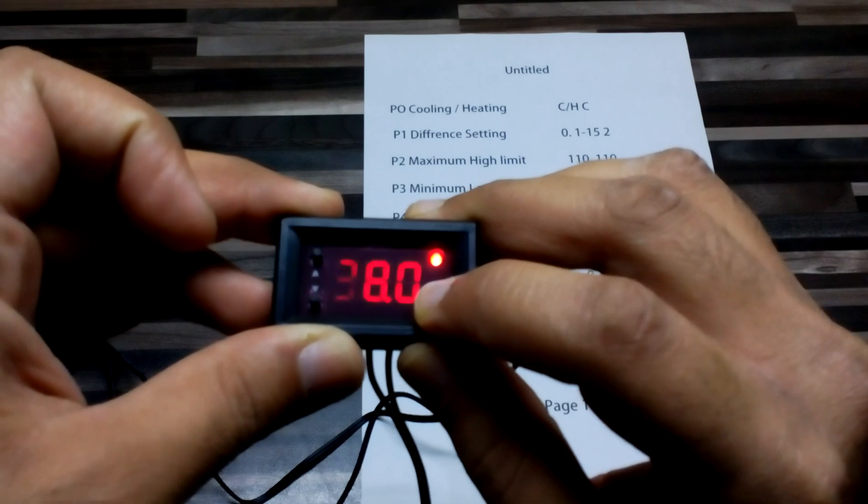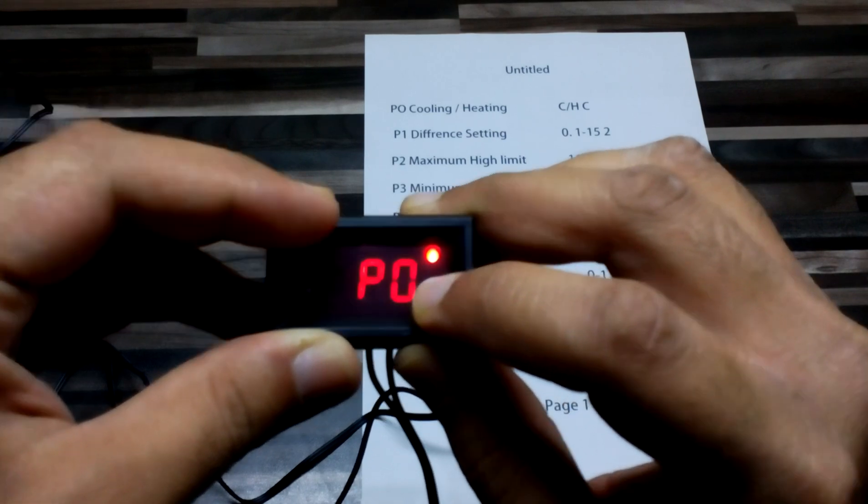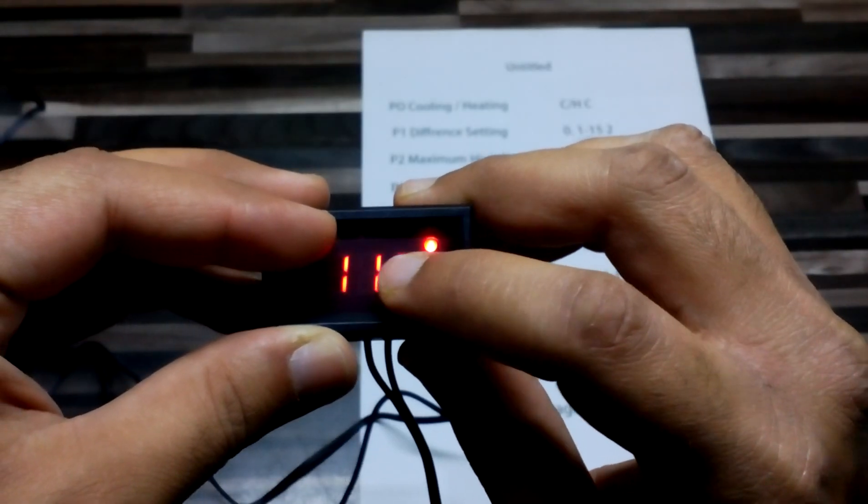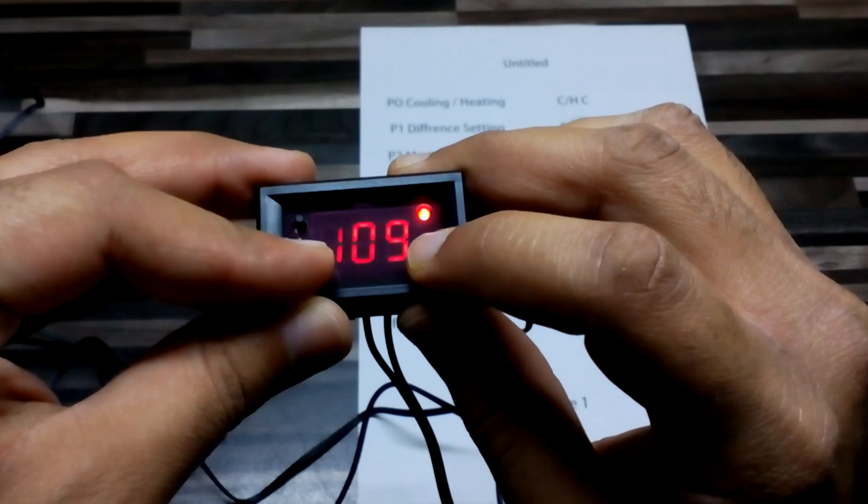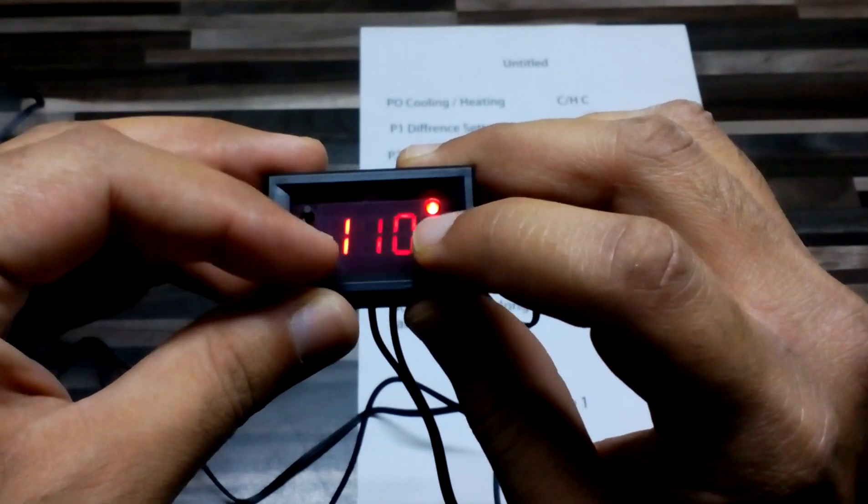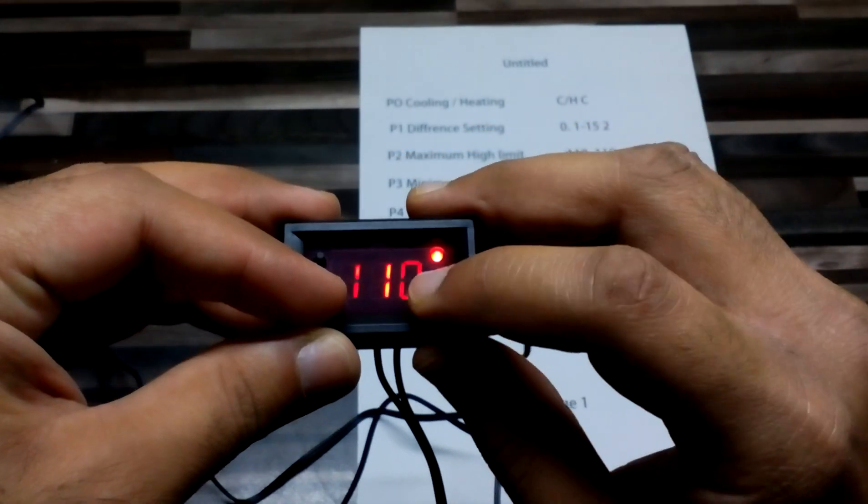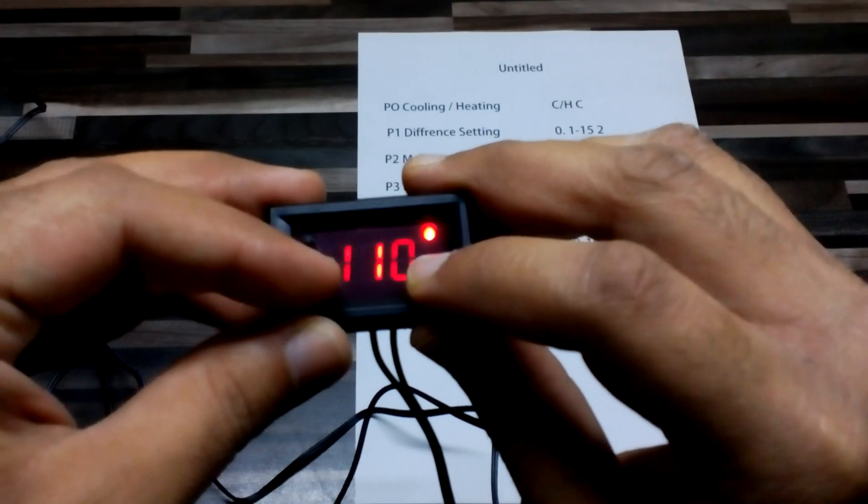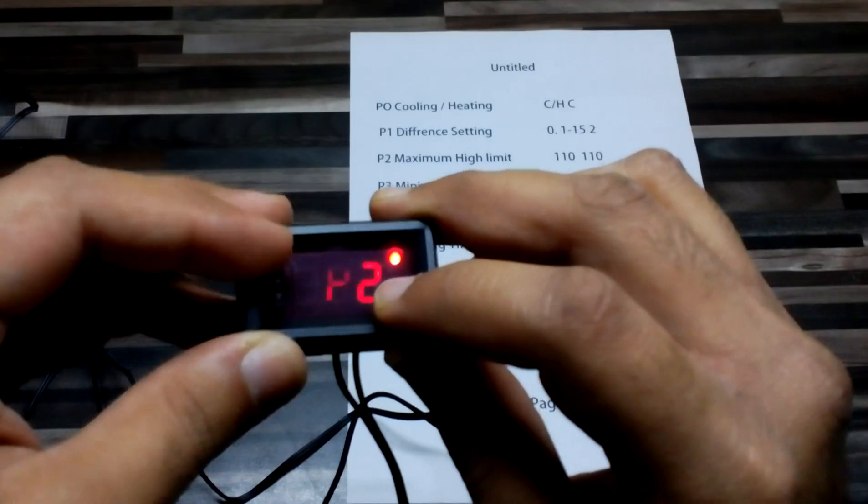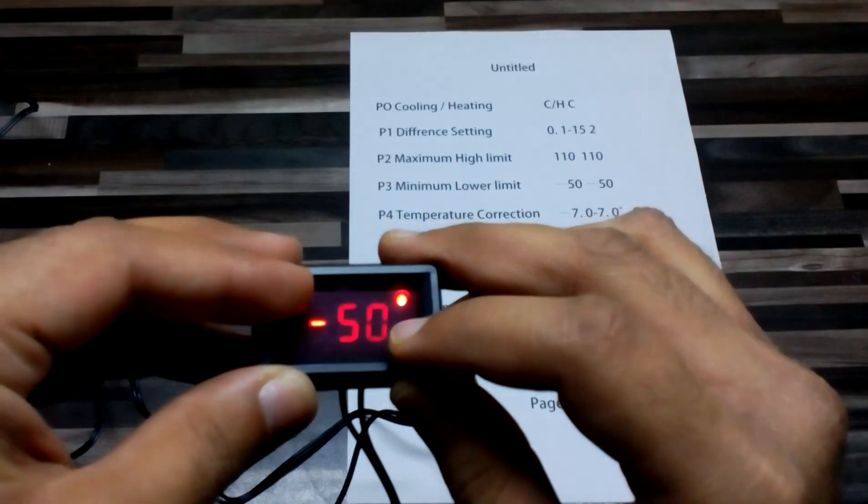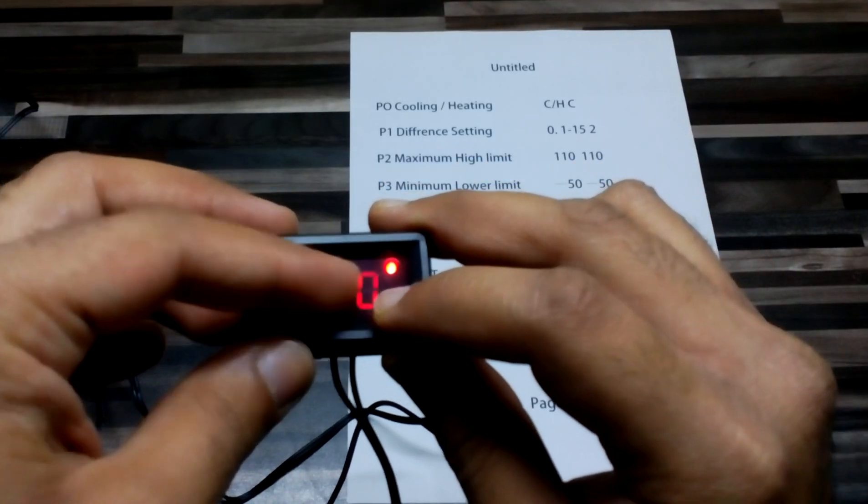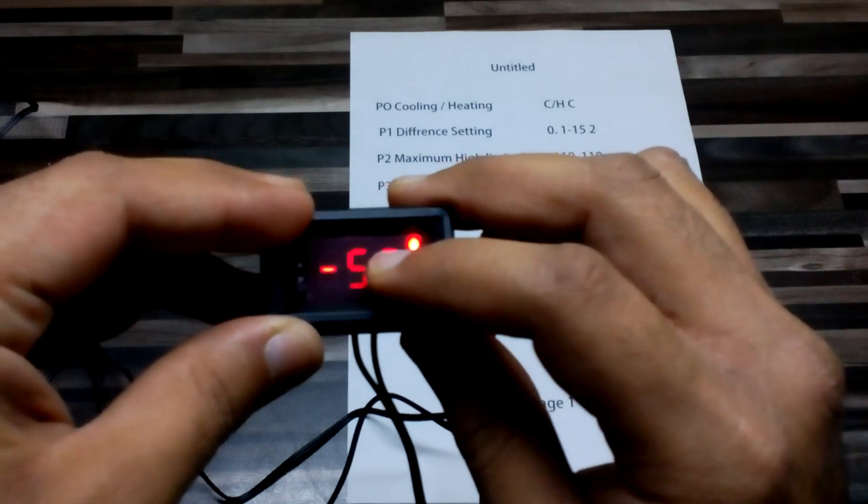On P2 maximum setting, we can set the highest maximum, which is 110 Celsius. If you're using it in an oven or something like that, it will only work up to 110 Celsius, not over that. On the minus side, if we're using refrigeration, we can only go to maximum -50, not less than that.